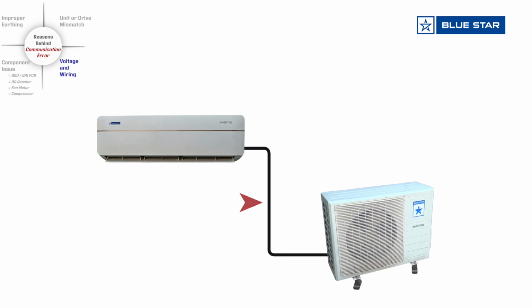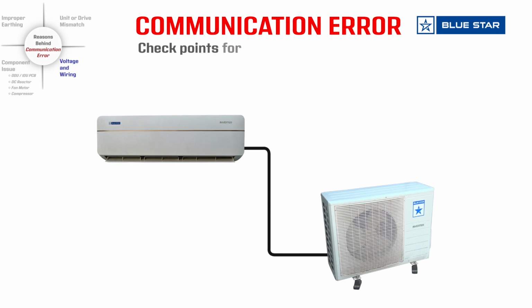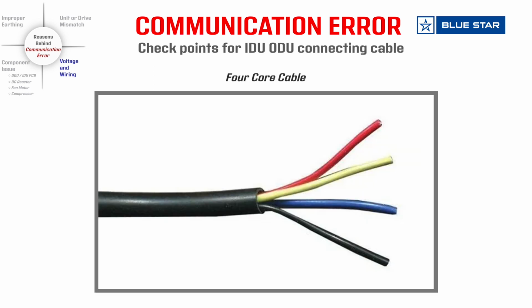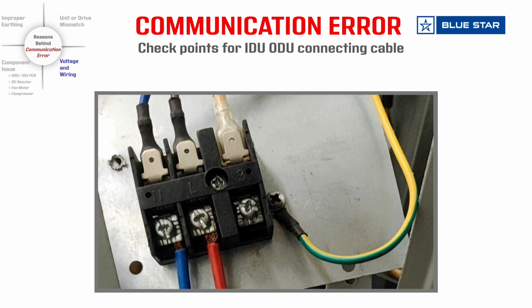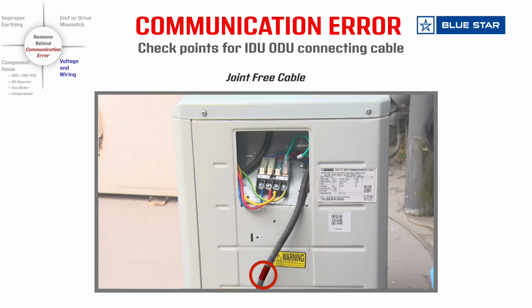Sometimes the cable connecting the IDU and ODU could lead to a communication error. Here are a few points to check on the IDU and ODU connecting cable. Cable should be made of 4 cores. If any one of the wires is not connected, it will lead to a communication error. So check if all wires are connected properly. Cable should be joint free.